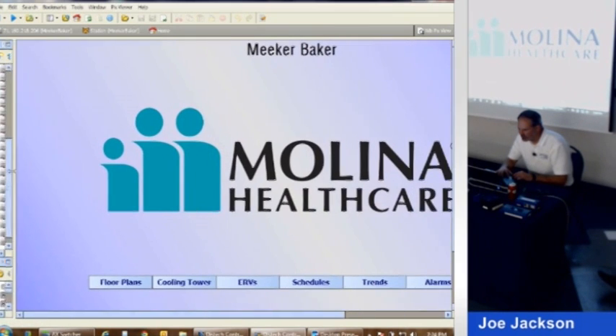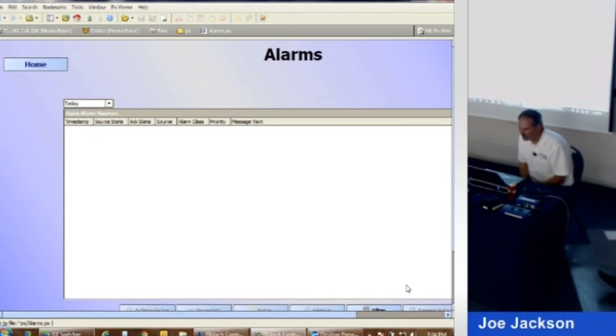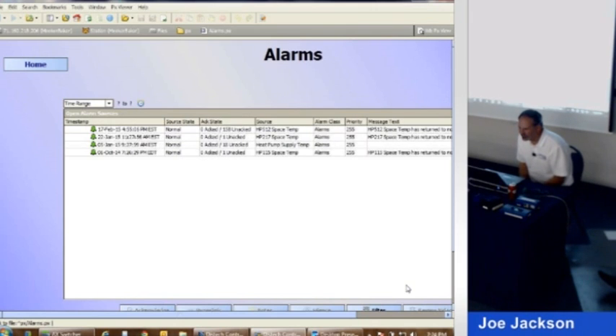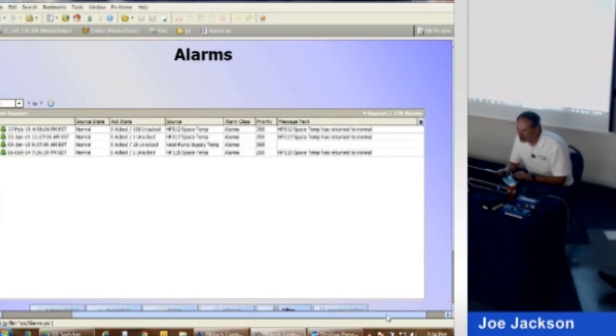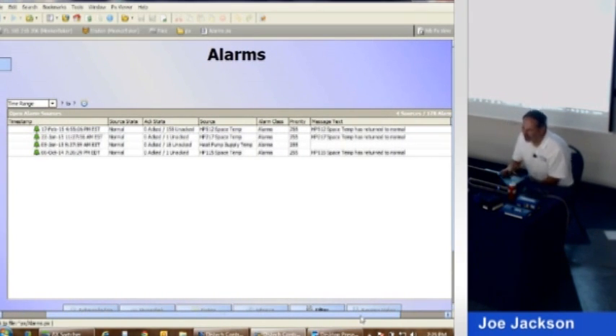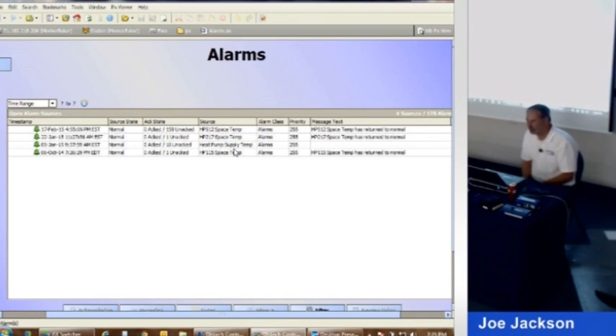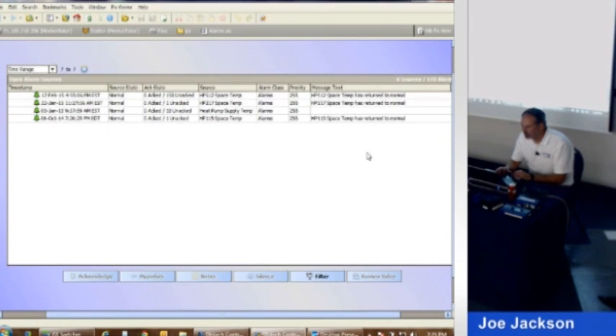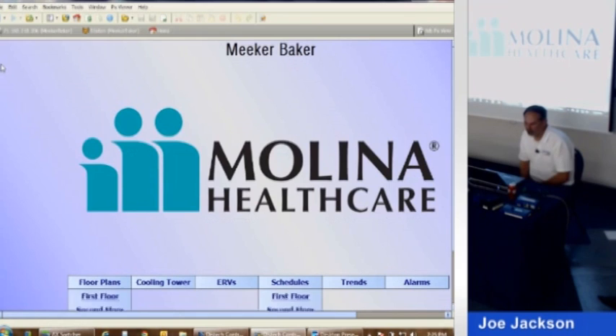And finally, we'll look at alarms. Hopefully there aren't any. It'll actually probably have a couple of things we call ping failures. Nope. So I've got a couple of space temperature alarms. Actually, it shows where it returned to normal. Everything's in green. At some point in time, that must have gone into alarm. Looks like the supply temperature to the heat pumps had gone out of whack at one point in time, has now come back to normal. Normally those alarms would stay there. Somebody must have acknowledged them. These are set to call out to the maintenance facility at night if they want to. So hopefully, if we do a good job, the systems are easy to operate with just a very little training.